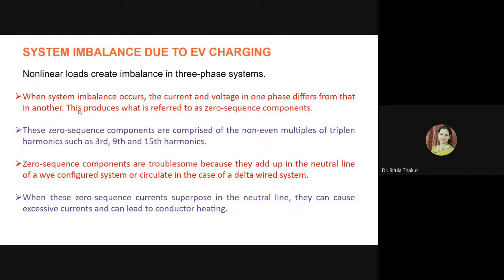Now, apart from harmonics, there are also imbalances created by EV charging. As in one of the previous slides, we have seen that harmonics and imbalance in the three-phase systems are some of the results of EV charging in the distribution system. Now, how does this imbalance affect things? We know that whenever system imbalance occurs, the current and voltage of one of the phases differs from another. Otherwise, all of them are in phase with each other. But whenever such imbalance occurs, it leads to zero sequence components. These zero sequence components are nothing but the odd multiples of triplen harmonics, such as the third, ninth, and 15th harmonics.